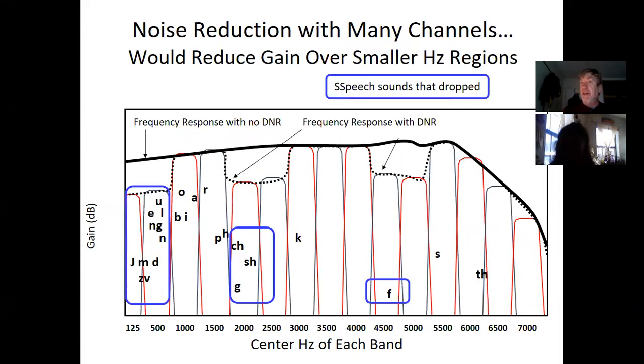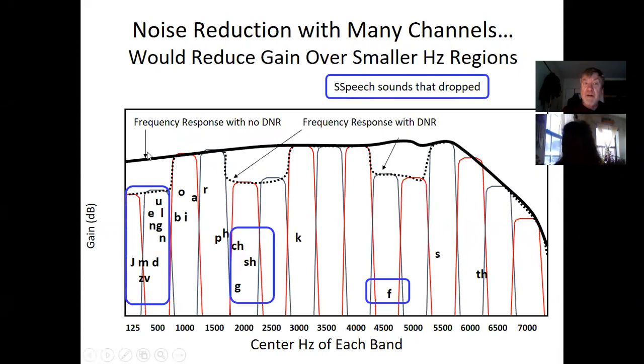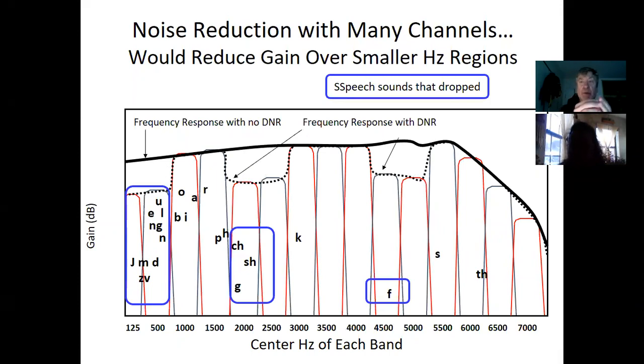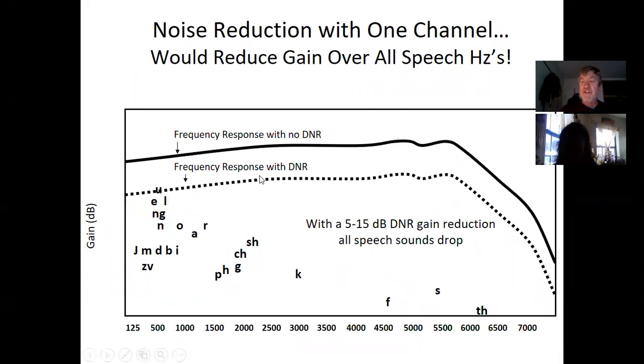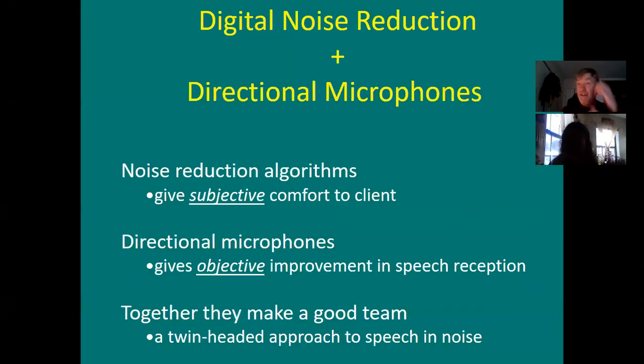With multi-channel DNR, the steady-state noise is picked up in specific channels and gain is reduced in those narrow frequency slivers. You're removing less of the baby with the bathwater, but still — any speech in those channels is also reduced along with the noise. So you're removing less speech, but it's still somewhat counterproductive. The final summary: digital noise reduction gives subjective comfort; directional mics give objective SNR improvement.